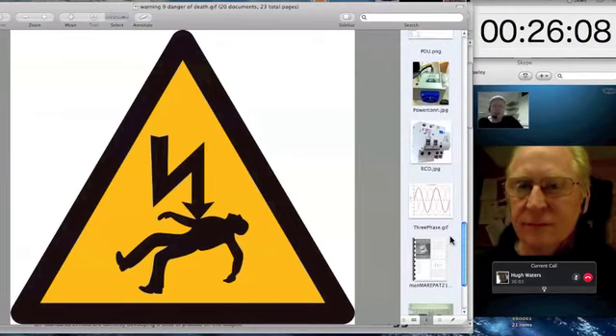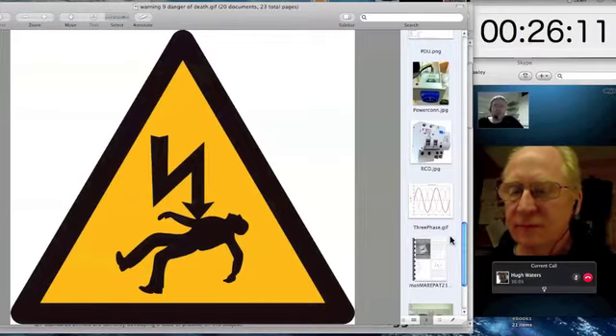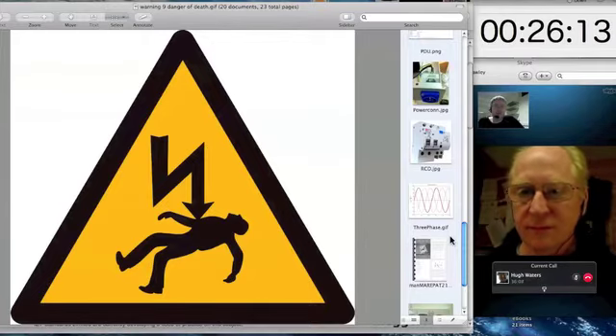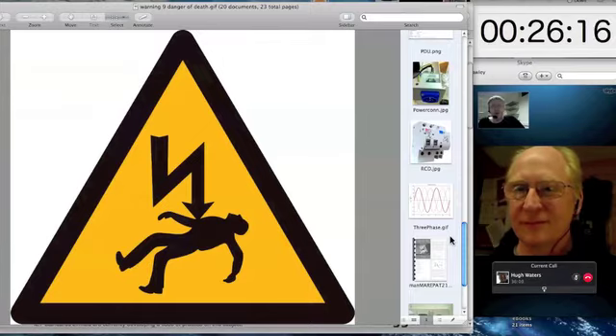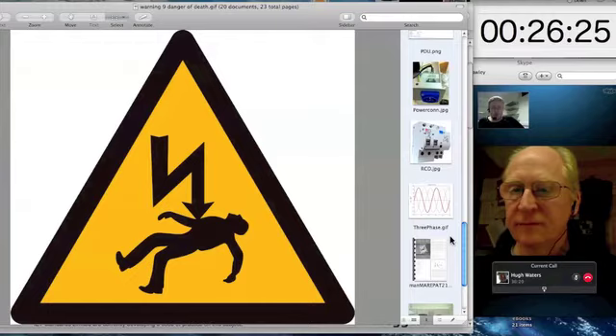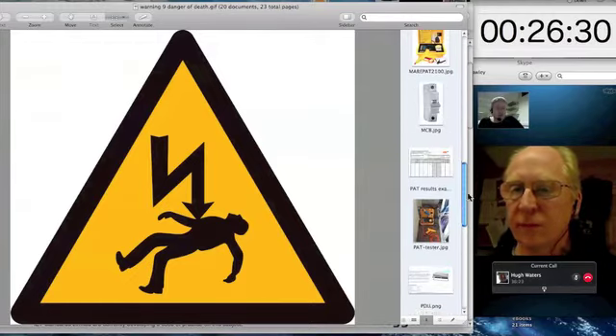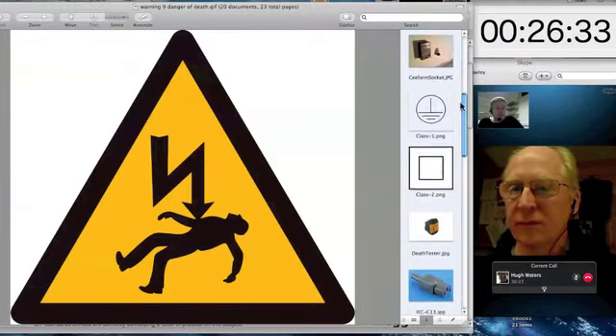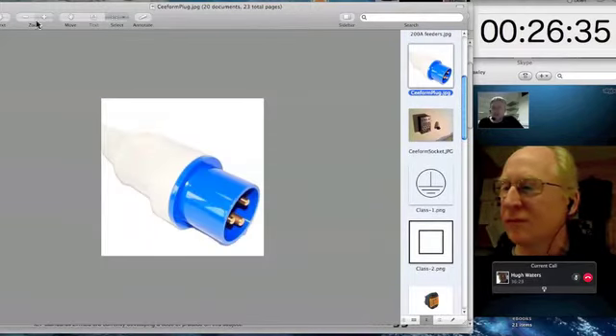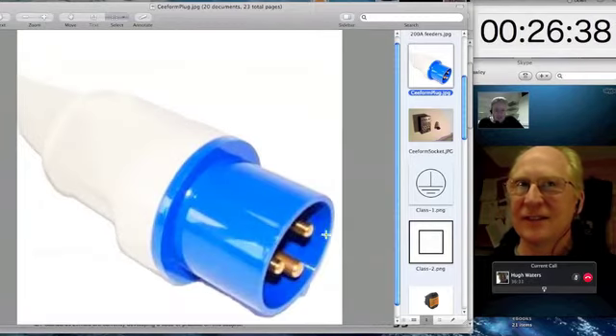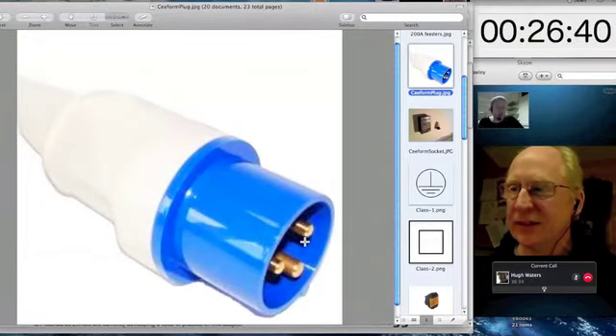That's a little bit misleading, because they assume that means the old-fashioned earthing spike that's been sunk into the ground in the yard outside. But that was the standard for mains probably until the late 70s. But for many, many years now, the earth that arrives at your facility, that safety earth, that third connection, the third pin on any mains connector. So I'll pop up a different style of mains connector just so we can. That's a C-form connector, C16 amp, otherwise known as a commando connector. That's what electricians refer to it as. The big thick pin there, that's the earth.